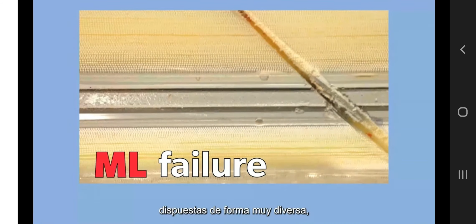Inside the membrane lung, we have layers of small diameter hollow fibers diversely arranged for transverse flow oxygenators or axial flow oxygenators. A healthy membrane lung allows for gas exchange via diffusion through these fibers from the gas phase into the blood phase for oxygen and from the blood phase to the gas phase for carbon dioxide. Thrombotic, fibrin or cellular deposits on hollow fibers worsen gas exchange, impairing membrane lung performance.